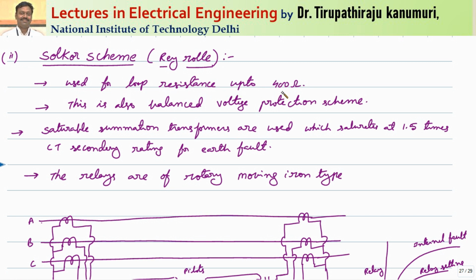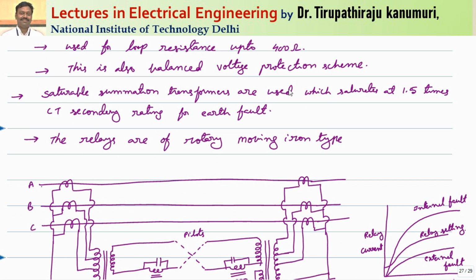This is similar to the translay scheme, the only difference being that it is a little bit simpler when compared to the translay scheme. But the limitation of this system is that it can be used only up to a loop resistance of 400 ohms. That means it can be used only for very short lengths when compared to the translay system. So this is also a balanced voltage protection scheme, similar to the translay system.